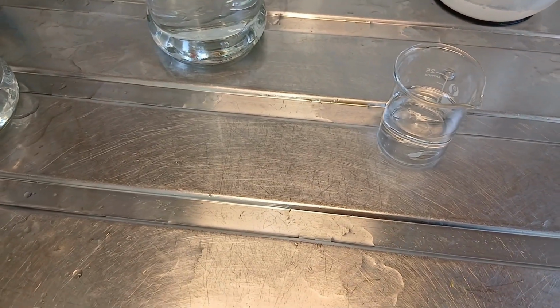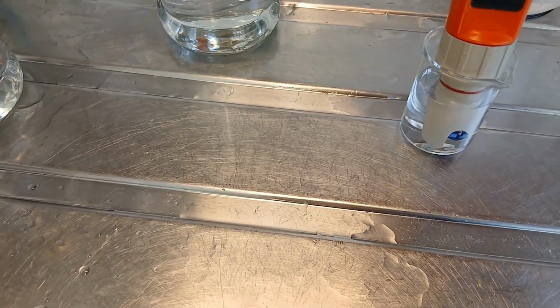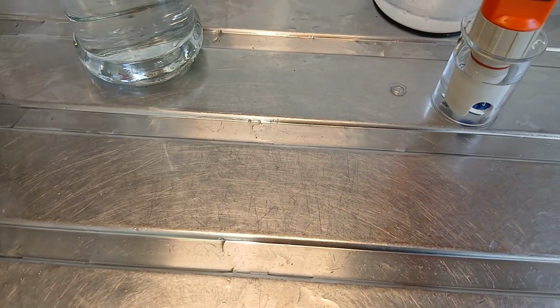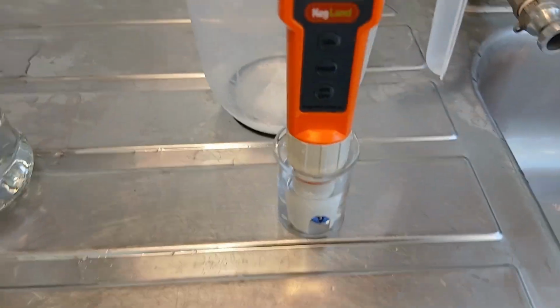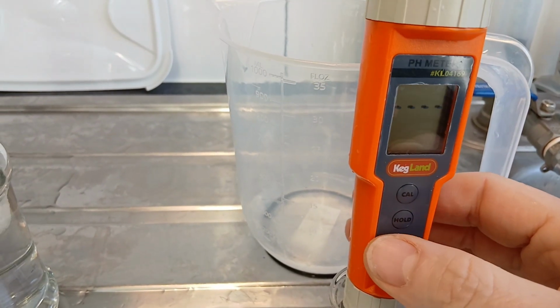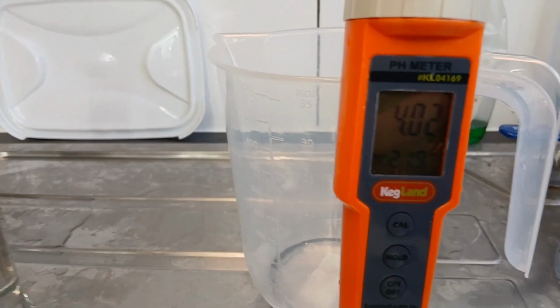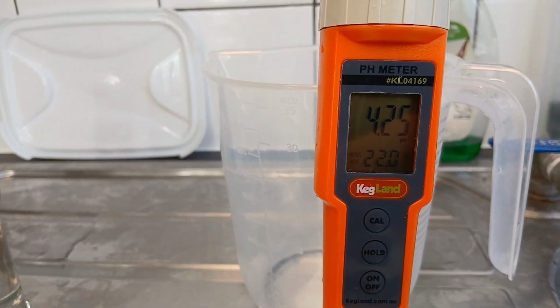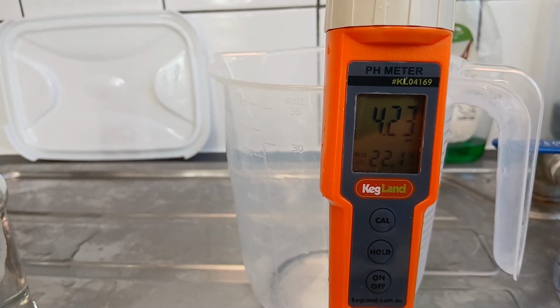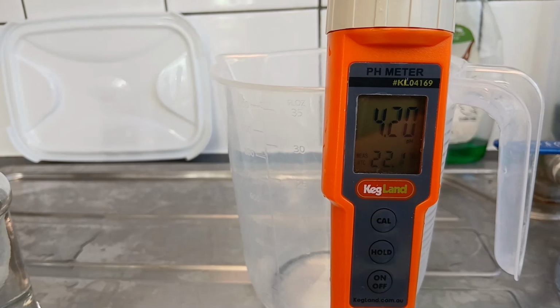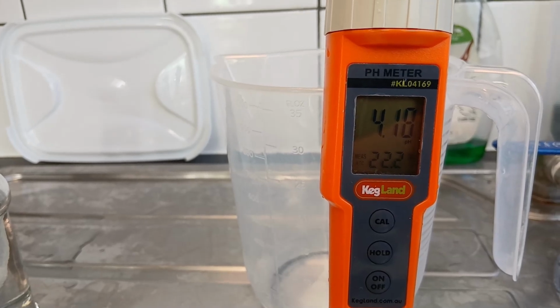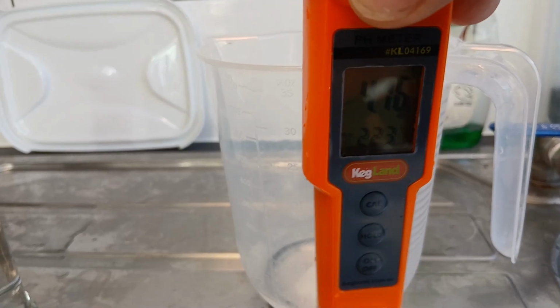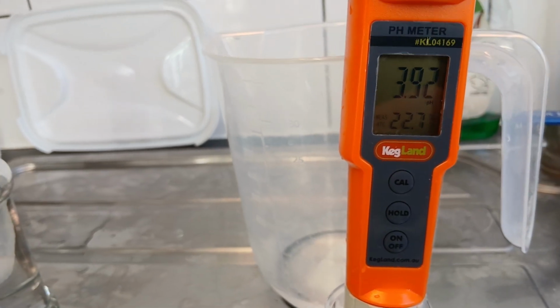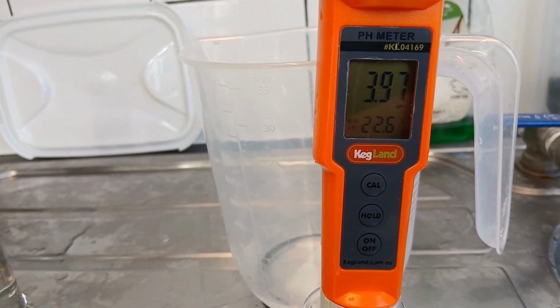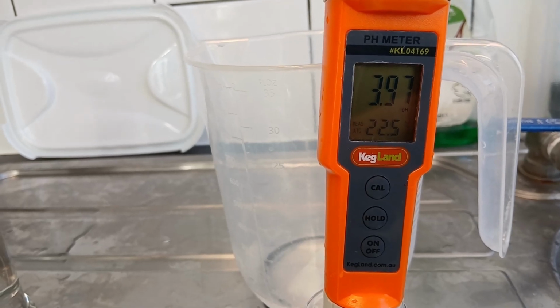So we've put some 4.01 pH in here this time. So we've got the pH meter back in, and let's turn it on. And okay, it's coming a little high. It is dropping back down again. Now I assume because we've been measuring a high pH previously, the electrode needs time to respond to that. Bit of a shake, 3.92, we've got 3.94, 3.96. Remember, we're looking for 4.01.